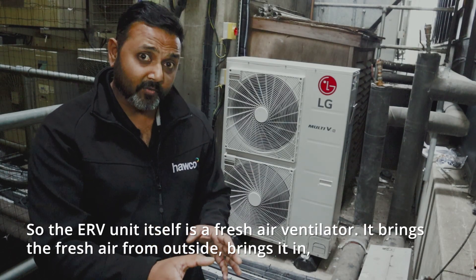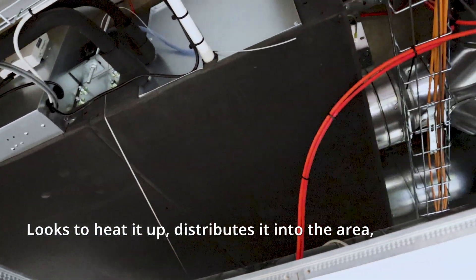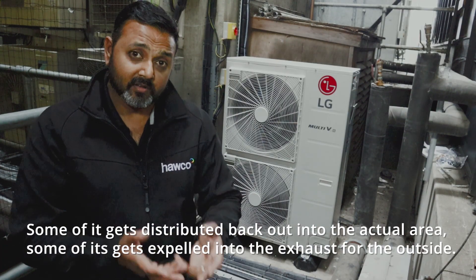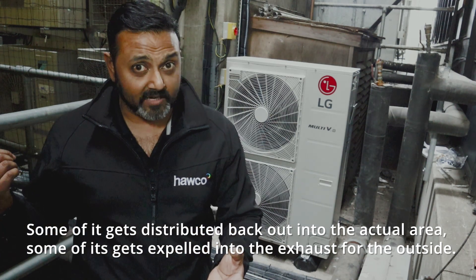The ERV unit itself is a fresh air ventilator. It brings fresh air from outside, brings it in, heats it up, and distributes it into the area. The heat that's already in the area gets brought up into the return — some of it gets distributed back out into the area, and some of it gets expelled into the exhaust for the outside.